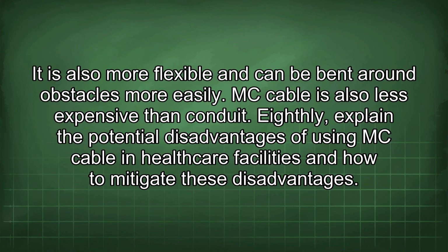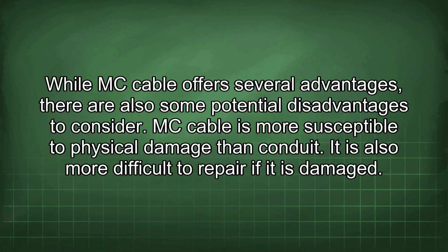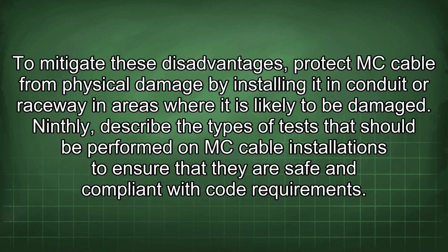Eighthly, explain the potential disadvantages of using MC cable in healthcare facilities and how to mitigate these disadvantages. While MC cable offers several advantages, there are also some potential disadvantages to consider. MC cable is more susceptible to physical damage than conduit. It is also more difficult to repair if it is damaged. To mitigate these disadvantages, protect MC cable from physical damage by installing it in conduit or raceway in areas where it is likely to be damaged.